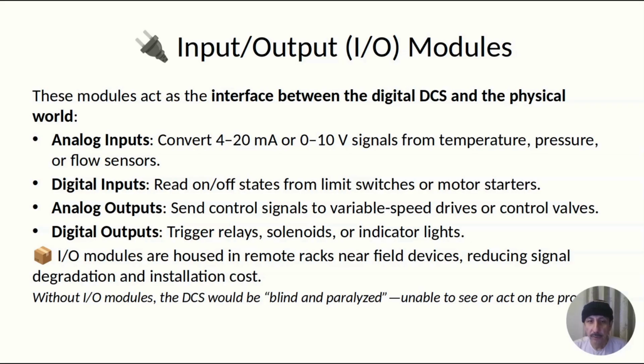The I/O module converts the analog signal into a digital value that the controller can understand. For example, 12.5 milliamps means 150 degrees Celsius. It is important to understand from the physics point of view that when you have a current loop, it doesn't matter how long your wire is or even if you change it or the condition of the wire changes. If it's going to be 12.5 milliamps, it's going to be 12.5 milliamps over the whole loop.